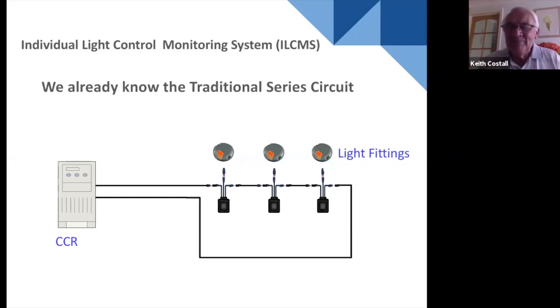Good question. Now, there is some guidance on this from ICAO and from the IEC in the technical specification 61820, and ICAO in the Aerodrome Design Manual Part 5 for electrical systems. The acceptable insulation resistance value for a primary circuit is based upon a calculated value. And the calculated value is based upon the number of transformers that you have in the primary circuit and the length of the primary circuit. So those two factors are in the equation.